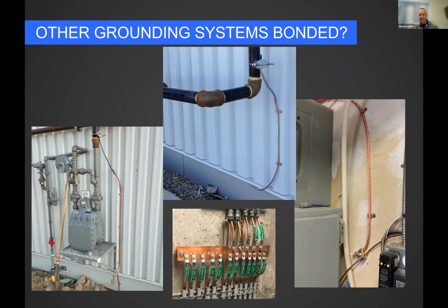There, of course, we bond up to the electrical ground on the right-hand side. That's on the interior of a kind of a residential facility. We just bonded up to the electrical ground wire at the ground floor. And then there's a standard main ground bus. That's from a big hospital in Vancouver that we did some work on. So the lightning protection came back and the grounding connected up on one of those nicely arrayed. Good work there.